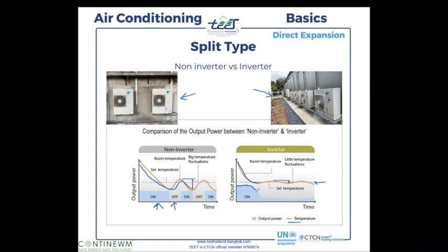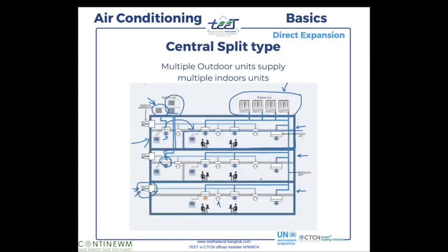And then after, it adapts the speed, you see, going down and increasing a little bit, decrease, increase, decrease, with much lower energy than a non-inverter type. And then you have a more comfortable temperature, okay? And you don't have this big peak of hot and cold, okay? So you save energy, it's more comfortable. So that is inverter.